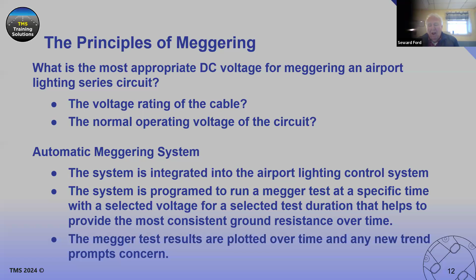One other thing about cables that Keith was talking about a minute ago, that paper I attached mentions that some contractors or airports, if you store cable, want to make sure the ends are covered so you don't get any water or dampness getting into the cable in the installation. You want to make sure that's sealed. Sometimes contractors do a high pot test on cable before they install it, just to make sure it meets the voltage requirements of the cable. Just a couple of other options that are out there.